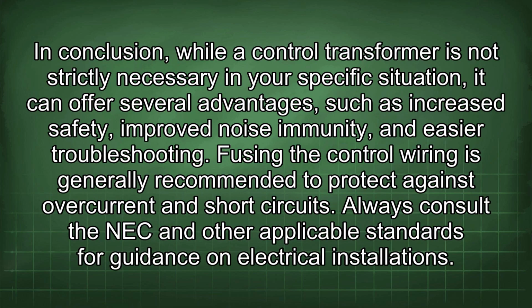In conclusion, while a control transformer is not strictly necessary in your specific situation, it can offer several advantages, such as increased safety, improved noise immunity, and easier troubleshooting. Fusing the control wiring is generally recommended to protect against overcurrent and short circuits. Always consult the NEC and other applicable standards for guidance on electrical installations.